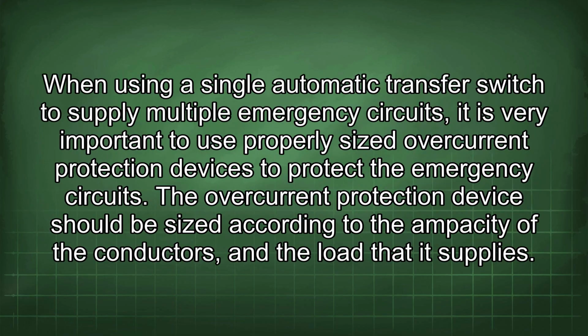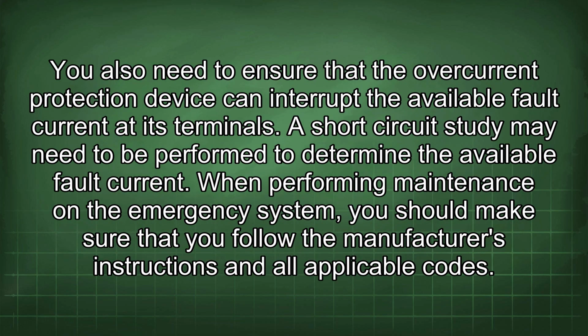When using a single automatic transfer switch to supply multiple emergency circuits, it is very important to use properly sized overcurrent protection devices to protect the emergency circuits. The overcurrent protection device should be sized according to the ampacity of the conductors and the load that it supplies. You also need to ensure that the overcurrent protection device can interrupt the available fault current at its terminals. A short circuit study may need to be performed to determine the available fault current.